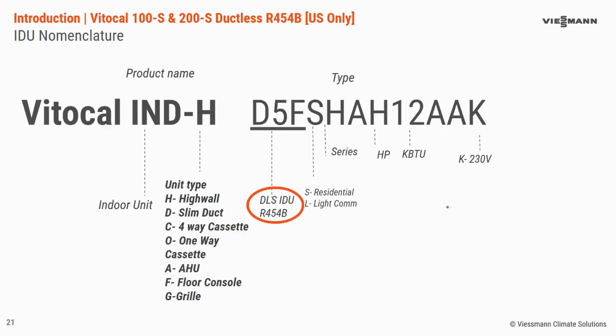The following model number uses a similar layout to the outdoor unit with some key differences for the indoor unit. The biggest being D5F instead of D5C. So if you see a D5F, you know that's an indoor unit, 454B. F for fan coil, that's the way I remember it. So D5F, you know that's an indoor unit.